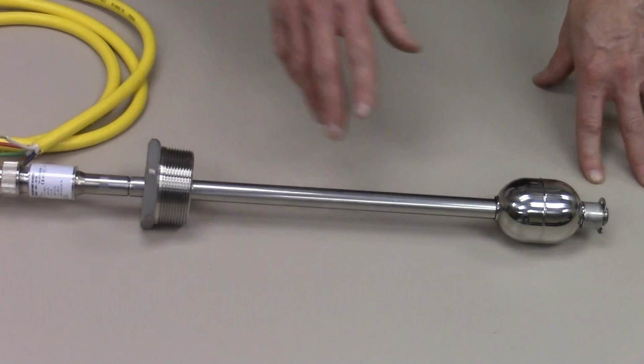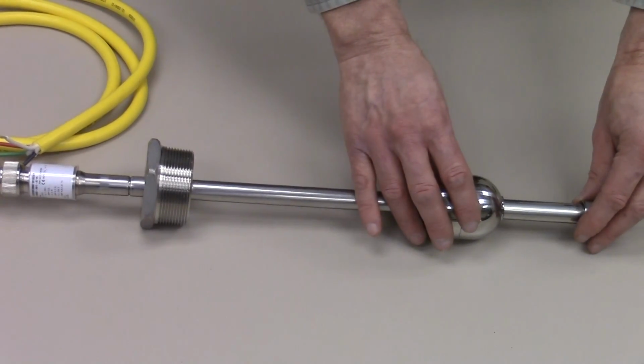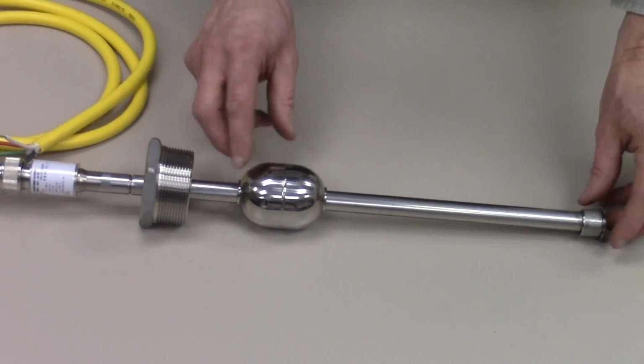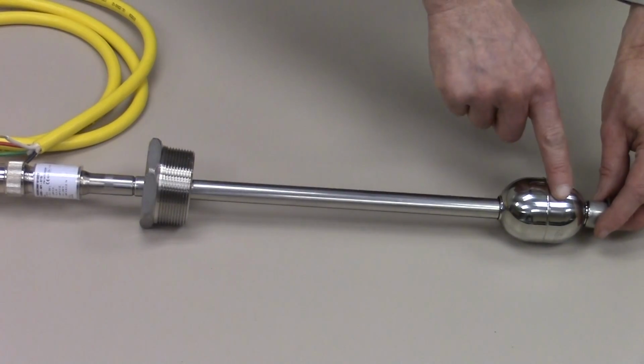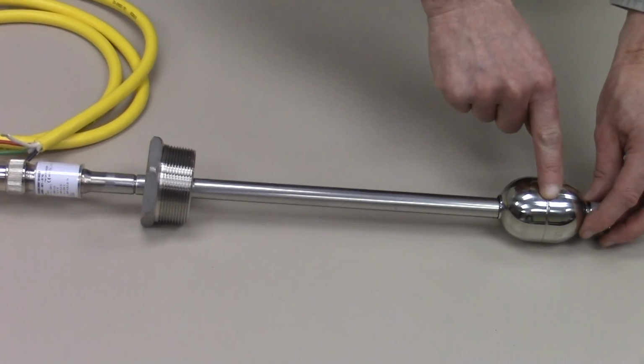We can set it with a 4 milliamp position raised, the 20 milliamp position can be lowered, or you can actually reverse the polarity on it. We can put 20 milliamps at the bottom and 4 milliamps at the top.